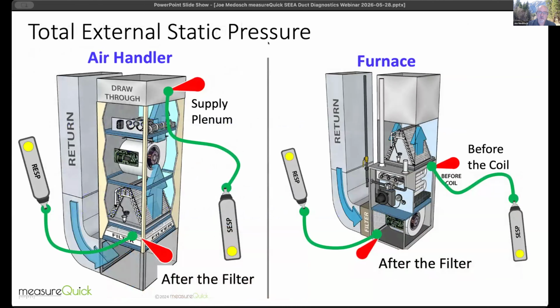The other thing you want to be doing is static pressure. If you're an HVAC contractor doing energy diagnostics, this should be done every time, because you never know when the homeowner will decide to get the brand new super MERV 3000 filter and block the airflow, thinking they're going to capture every particulate known to man. They only restricted the airflow, which caused not just airflow problems but a variety of dynamic problems, including what may show up in your refrigerant charge. We'll talk about that in a second, but this is one of the easier evaluations.